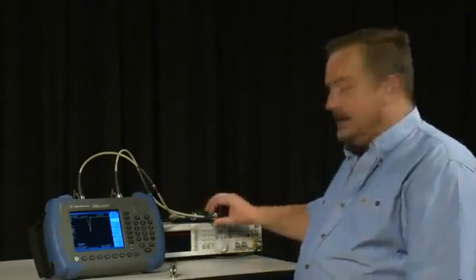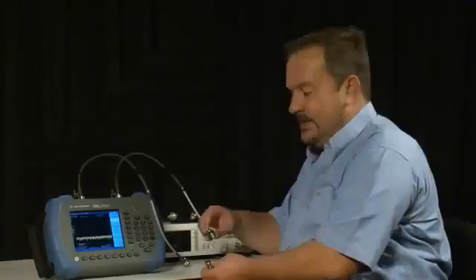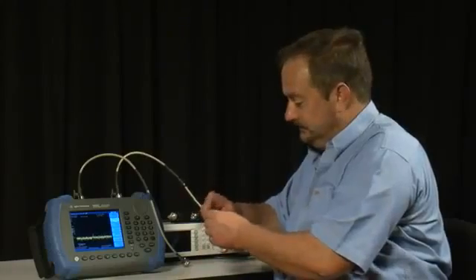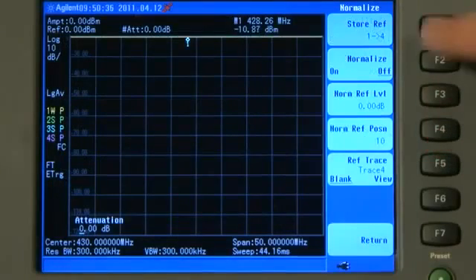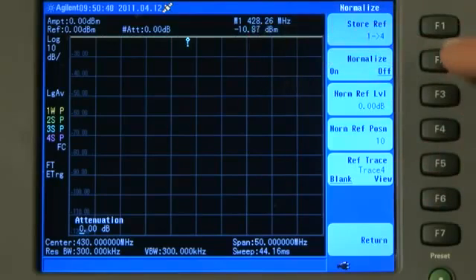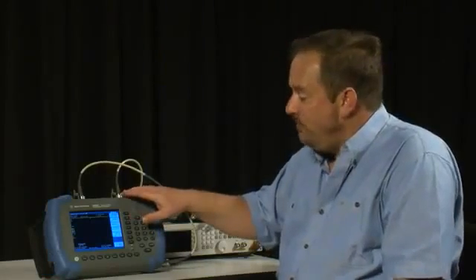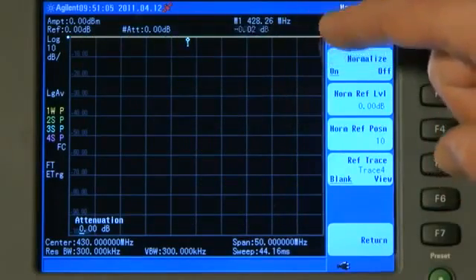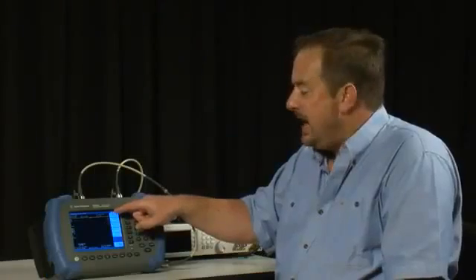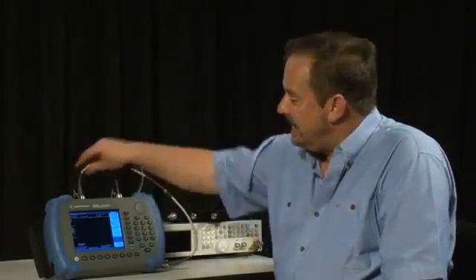So I will disconnect the filter and I will connect the through adapter. And if we press the Meas key, and then normalize, store ref 1 to 4, that saves the trace into the memory, and then press normalize on. The instrument has now normalized this trace. The trace is now at exactly 0 dB, right the way across the top of the screen, and is removing any losses or errors from the cables and adapters and the rest of the measurement setup.